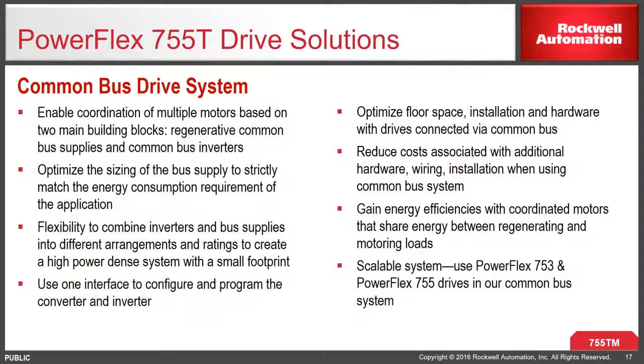Use one interface to configure and program the converter and inverter. Optimize floor space, installation, and hardware with drives connected via common bus. It reduces costs associated with additional hardware, wiring, installation when using a common bus system. Gain efficiencies with coordinated motors that share energy between regenerating and motoring loads. It's a scalable system. You can use a PowerFlex 753 and 755, both on a common bus system.